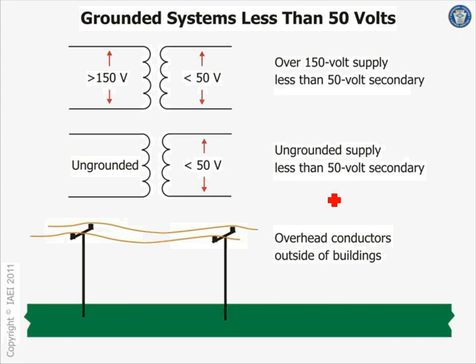Imagine a nuclear plant here, and that control circuit is controlling a nuclear reactor. And every time you have a ground fault, the control circuit can create more hazard, or a chemical plant, you know what I mean? Do you really want to ground this circuit here and take a chance that a ground fault on this control circuit will alter and interfere with the operation of a nuclear reactor or a chemical plant? So there's an exception. But if this is feeding your doorbell, there is no nuclear reactor there, or your sprinkler system. So if you're using 120 here for my sprinkler system, do I need to ground the secondary? No. Only if the voltage is 277. So any 120 primary, like my doorbell, I don't need to ground the secondary of my doorbell.